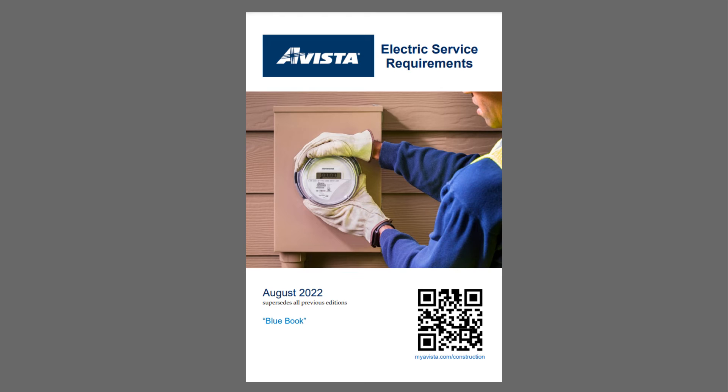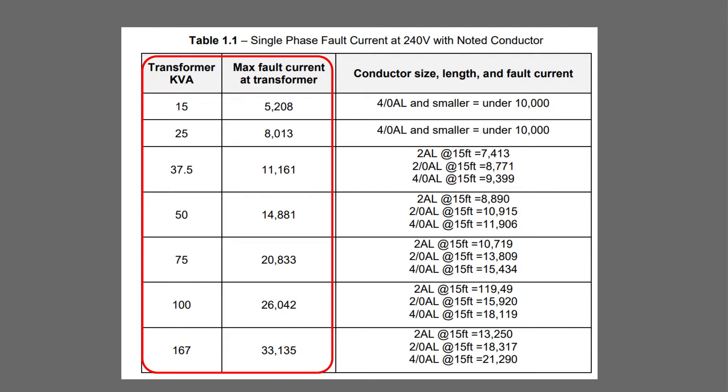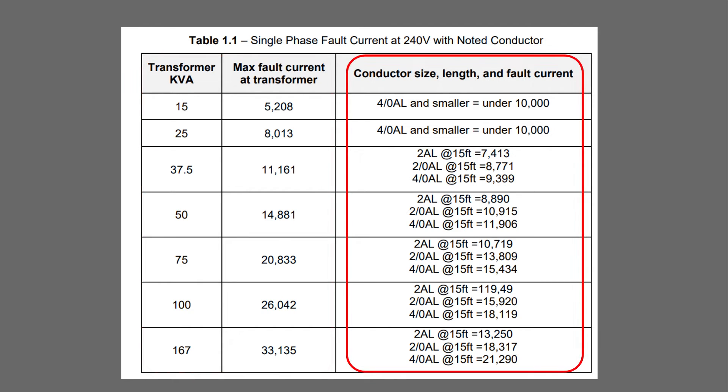So where can we find out how much fault current is available at the load side connections of a transformer? Many utilities will just publish the information for the particular brand and configuration that they use. For example, in the area of Eastern Washington where I live and work, Avista Utilities is one of the main electricity providers. They publish a directory they call the blue book, and I can look up the fault current based on type of service, KVA rating and voltage system. Also note these other columns, where they give some examples of how much the fault current drops after introducing a specific size and length for the service drop or service lateral.